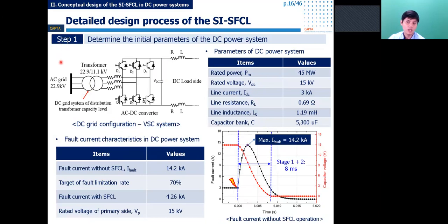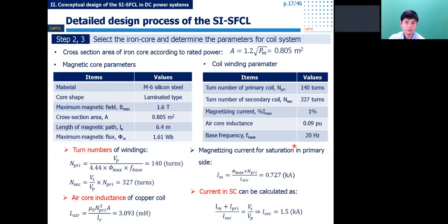In the detailed design process, firstly, the initial parameters of the VSC-based DC power system determine that the maximum fault current level without the SFCL operation is 14.2 kiloamperes. In the second and third steps, the parameters of the iron core and the coil system are determined. The SI-SFCL can be designed like a transformer. The iron core dimension is calculated based on the rated power of the DC grid, and the number of turns of the coil system and the operating current of the secondary coil can be calculated from the magnetizing property of the iron core and the selected fault duration.